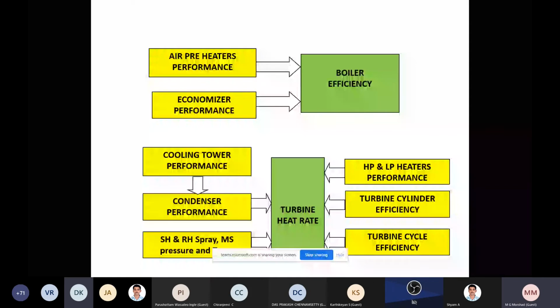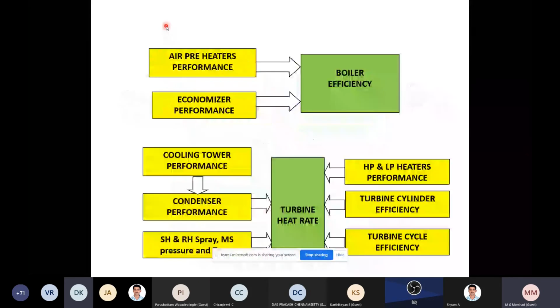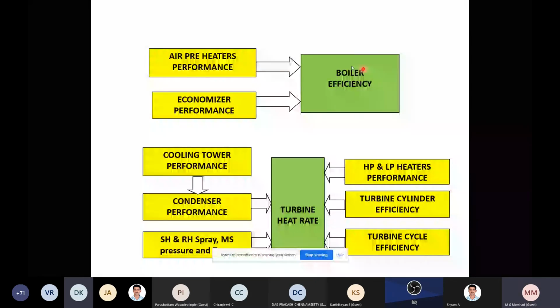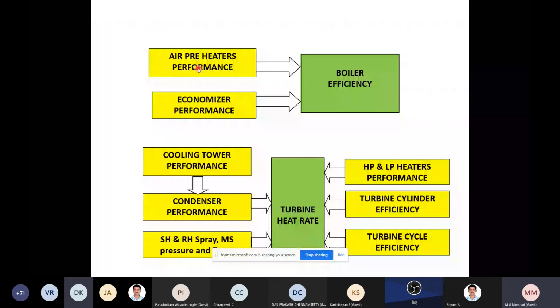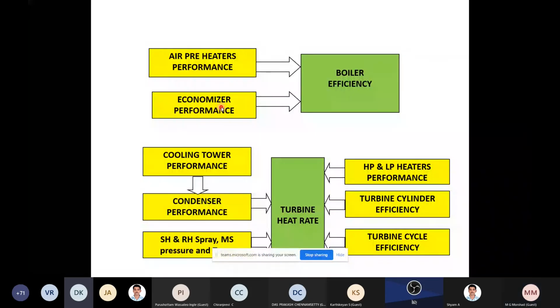Now, this is the scope I am telling you, this is the basic idea. Now, how to write the scope? See, boiler efficiency, you have to calculate it. Boiler efficiency depends on the air preheater performance and the economizer. So you have to prepare the scope for the boiler efficiency, air preheater performance, and economizer performance. So the boiler system should be covered. Okay, so air preheater and economizer, boiler efficiency, one set.